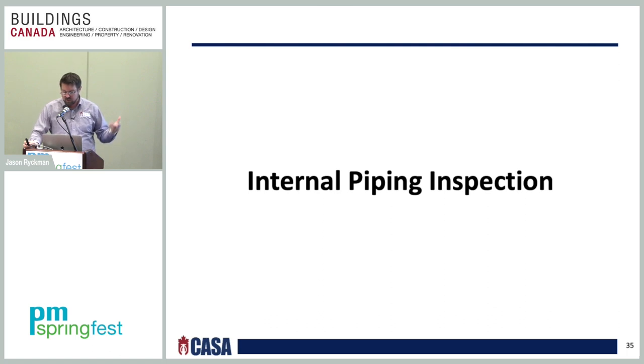Obstructions are addressed in Chapter 14, which identifies potential causes of piping obstructions, and requires an obstruction investigation, which is different from an internal piping inspection, which we'll get to a little later, if any of those situations exist. One of the unique things in the Ontario Fire Code that's different to NFPA 25 is on dry systems. In the Ontario Fire Code, the requirement for an internal piping inspection is every 15 years. In NFPA 25, it's every 5 years. So that's a major difference.